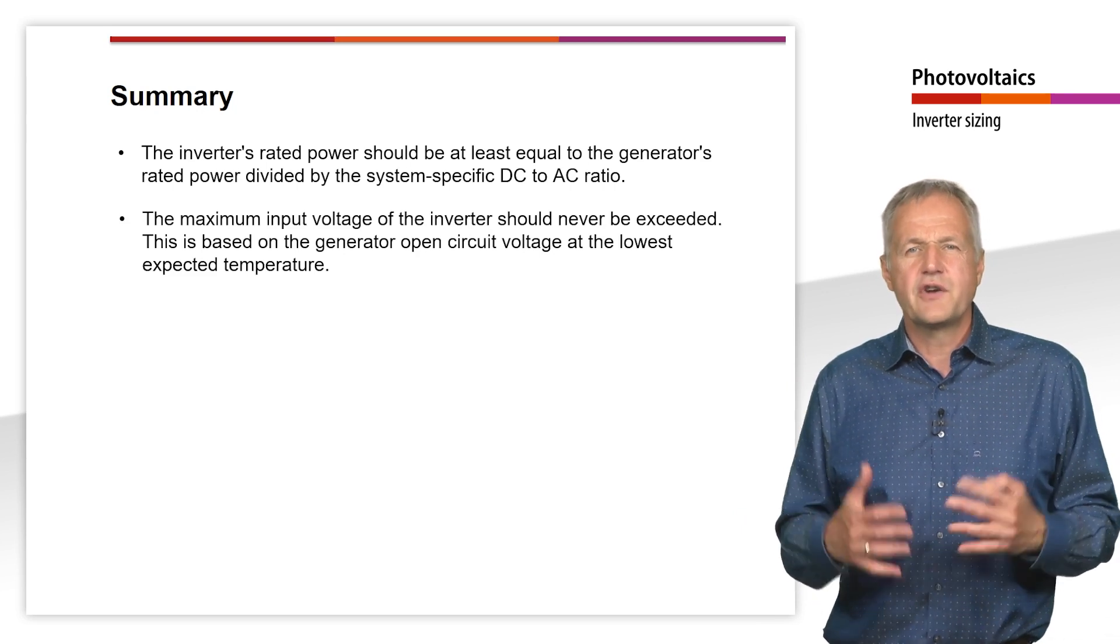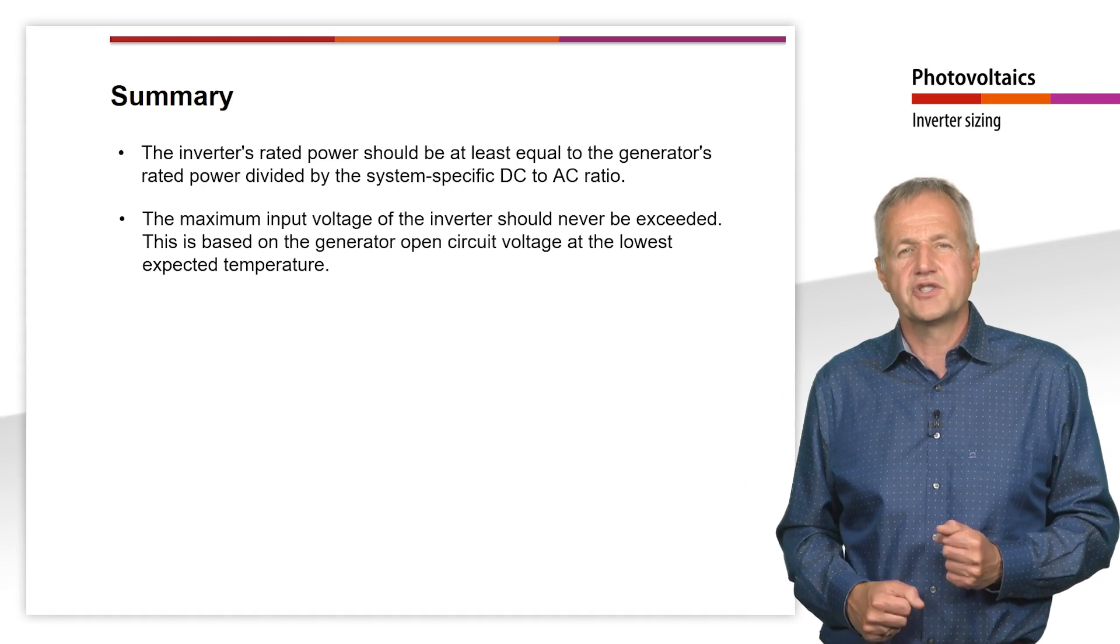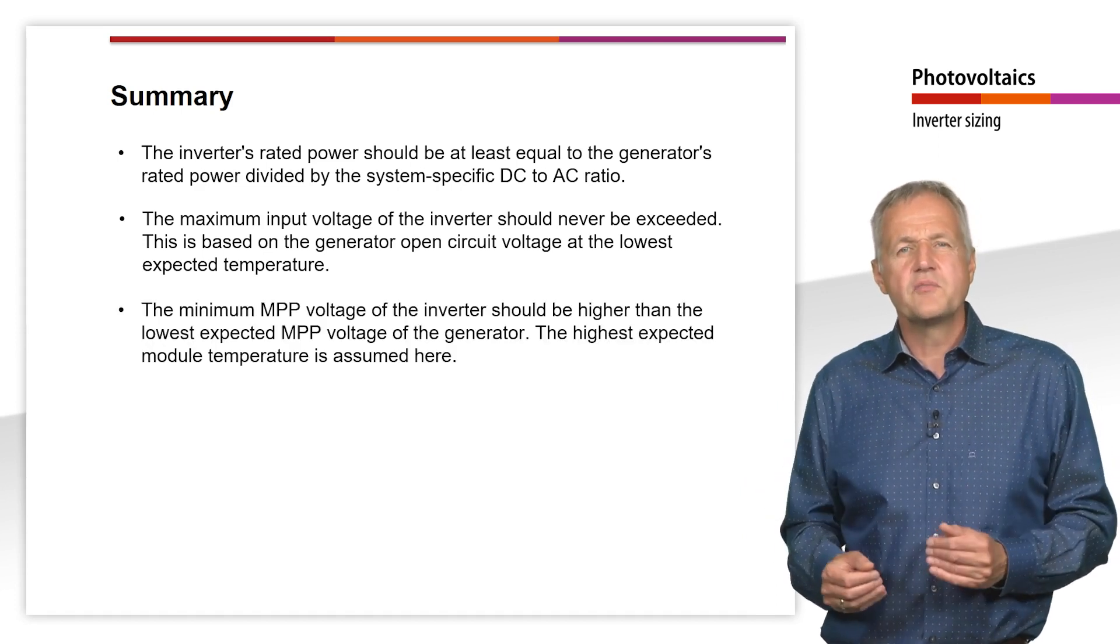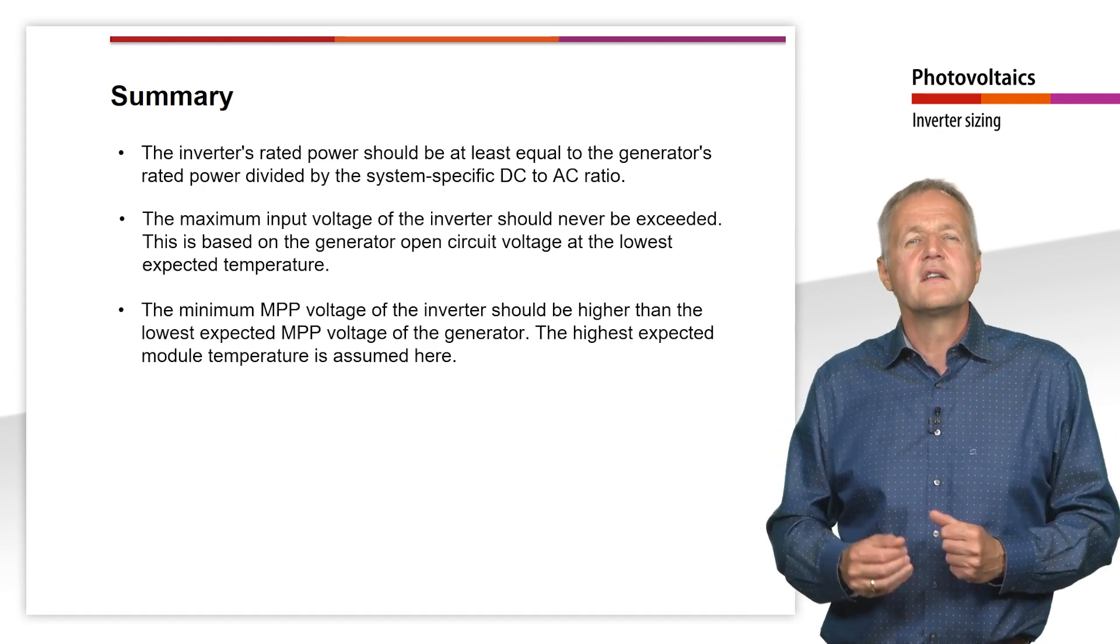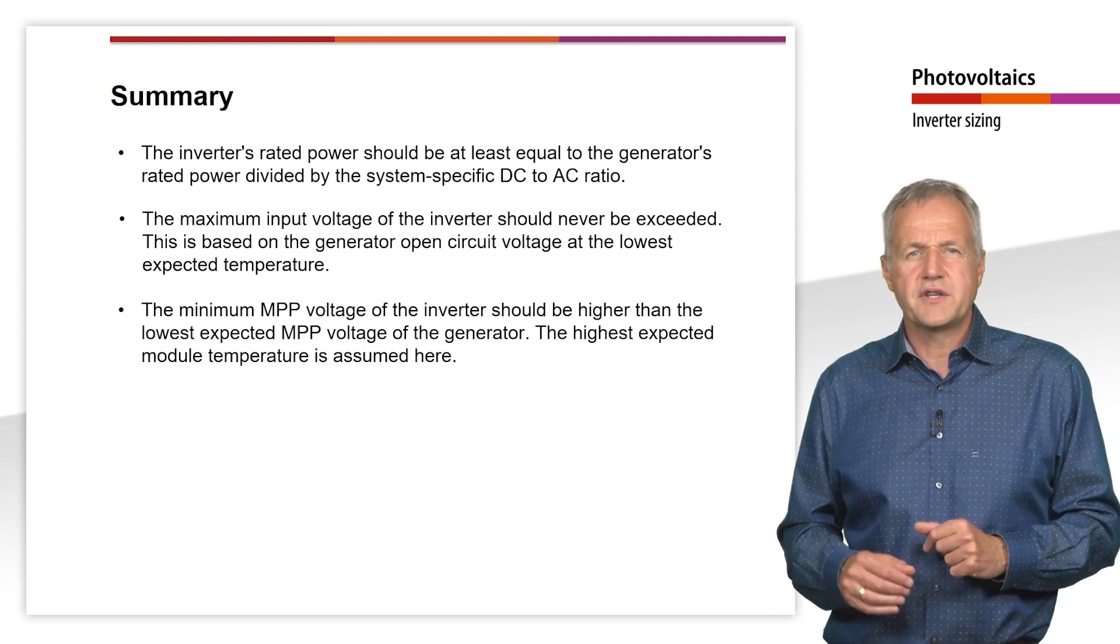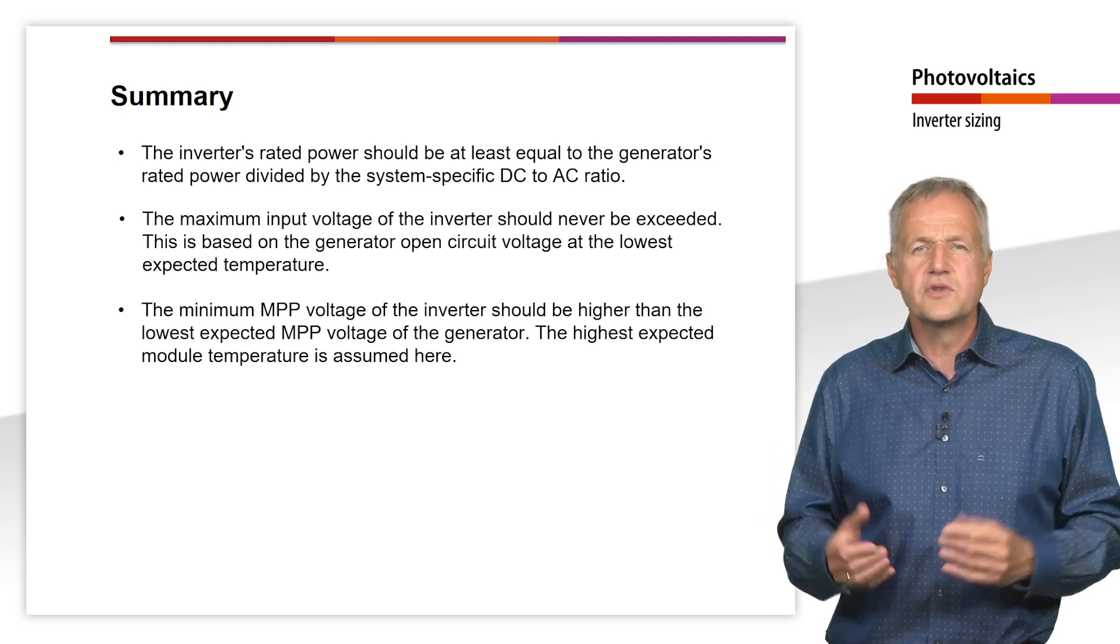This is based on the generator open circuit voltage at the lowest expected temperature. The minimum MPP voltage of the inverter should be higher than the lowest expected MPP voltage of the generator. The highest expected module temperature is assumed here.